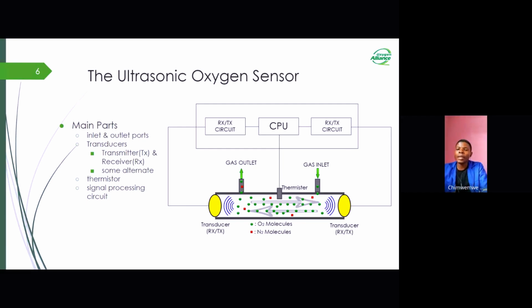Another thing that I should mention here is that some ultrasonic oxygen sensors have an extra part called a thermistor, or a temperature sensor. This temperature sensor measures how cold or hot the gas is, so as to adjust the oxygen reading to make sure it's accurate, even when the temperature changes. I'll talk about how temperature changes affect the reading of the oxygen concentration shown on the oxygen analyzer which uses this type of ultrasonic oxygen sensor.